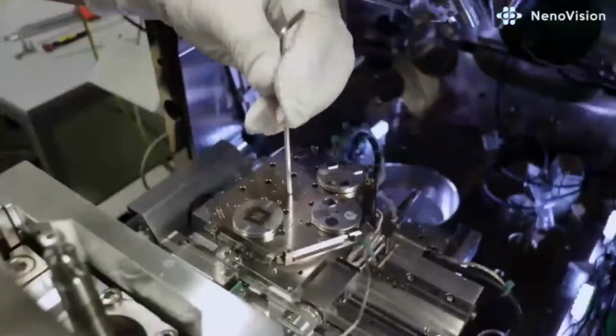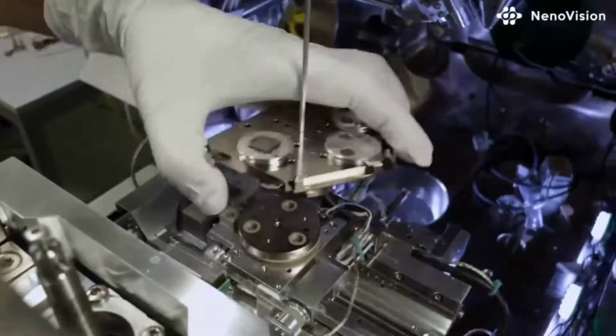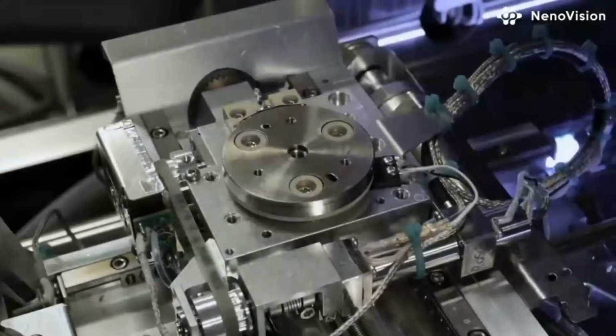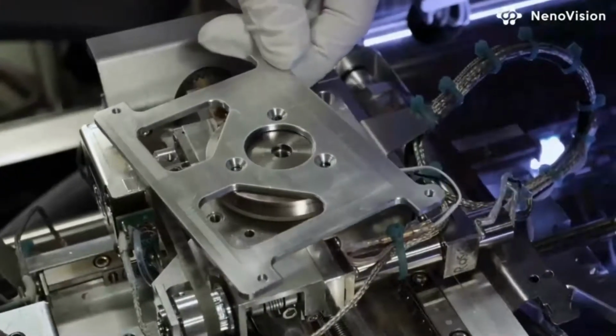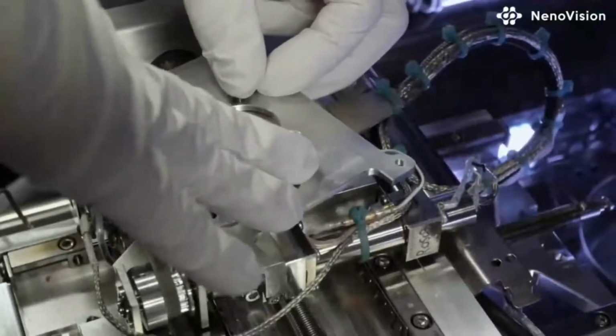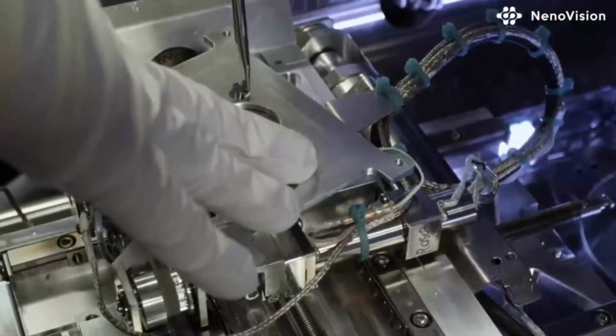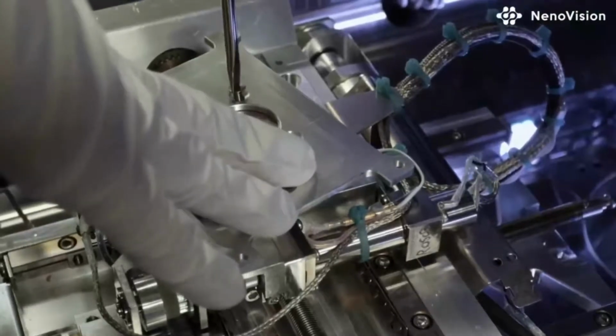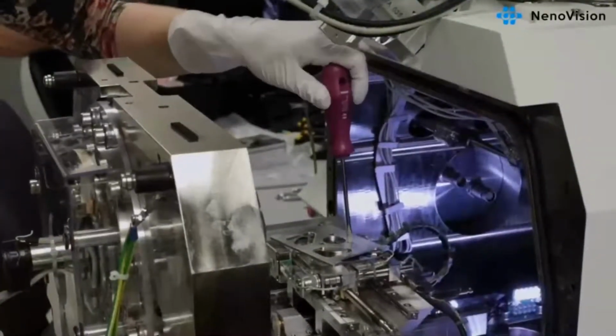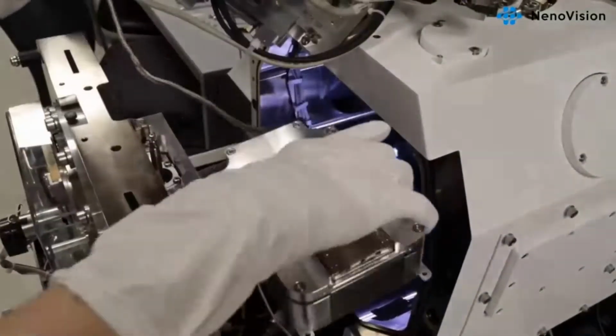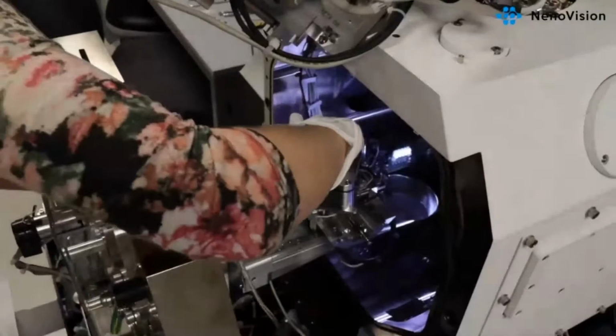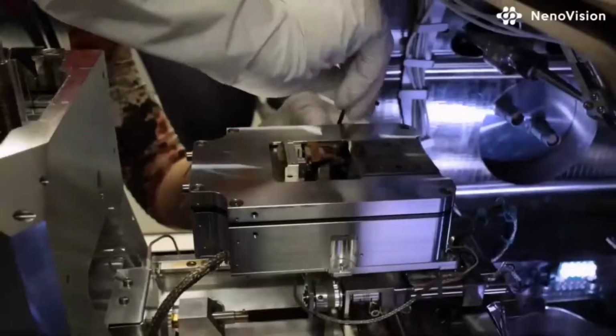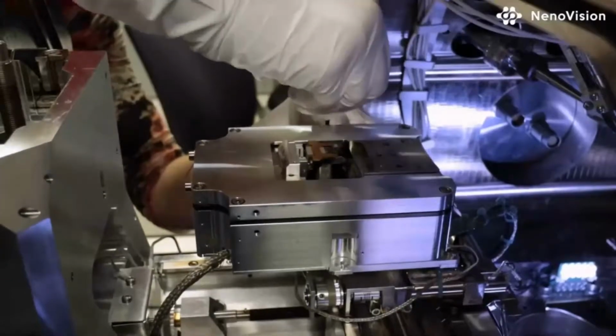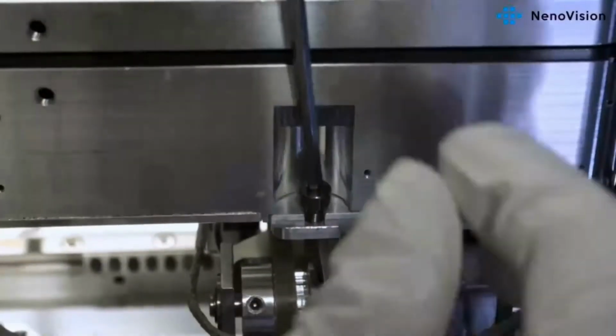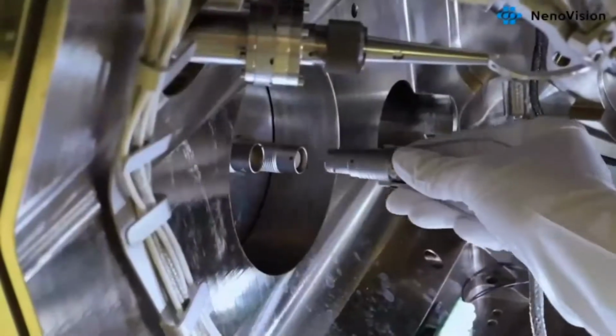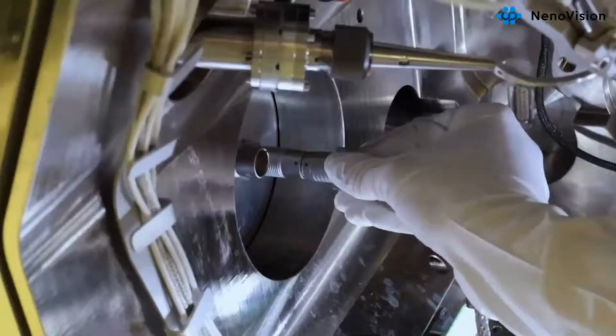We are going to continue with the installation, which has to be done by each user. The only thing which has to be removed is the SEM sample holder. First, we fix an adapter to the stage, which is rotated to a proper position, and we fix the LiteScope with 3 screws to the adapter. Finally, we connect the LiteScope cables into the feed-throughs leading to the Nanobox.